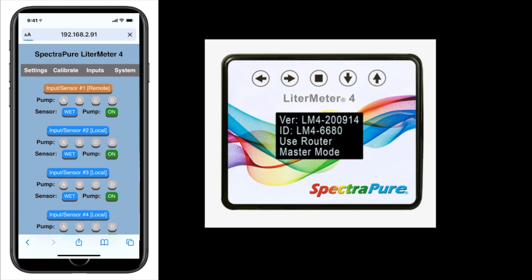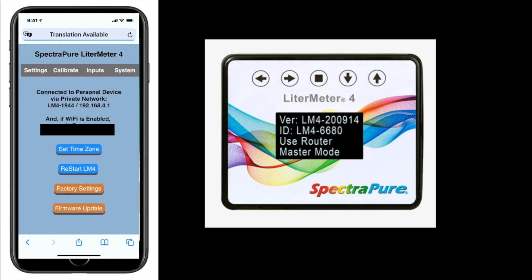If you hit calibrate, you can begin the calibration of the device. The calibration is quite simple: click the device you want to calibrate, hit begin, it fills to a specific amount, and then you enter what the amount was when it filled. You have to hit pump then calibrate to get to that specific pump. The inputs section is where you set up sensors — it's a lot easier to do on the phone than on the device itself. You select what kind of sensor it is; it could be a remote sensor from another LiterMeter. You can set if the sensor will be wet or dry and what you want the pump to do in each state — for any type of float sensor or optical sensor. The system settings section is where you set your time zone, view your ID and other info, reset to factory, restart, set up timers, and do firmware updates.